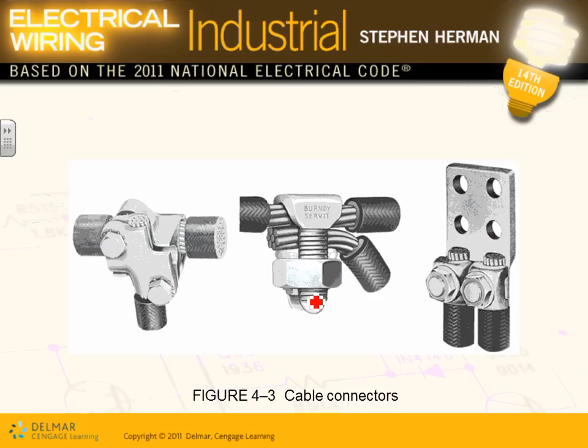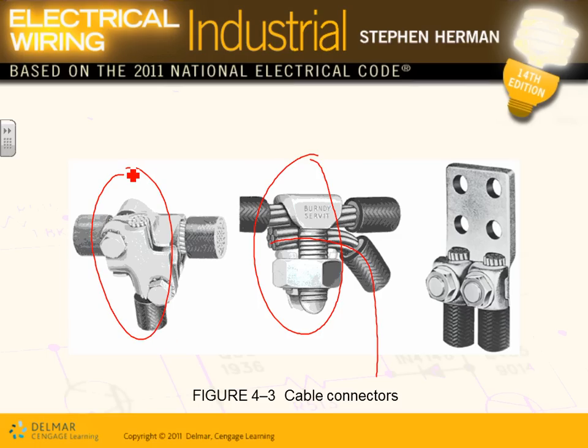We're not using the taps. When you're tying two cables to each other, the lugs have to be rated for that. Can you guys see that? Here's how you tap a feeder. You get the insulation out and then you take your tap. Here's another way of tapping that feeder to another lug. Or here's a main lug, and a third way of tapping that feeder, coming in, coming out, sub-feed.